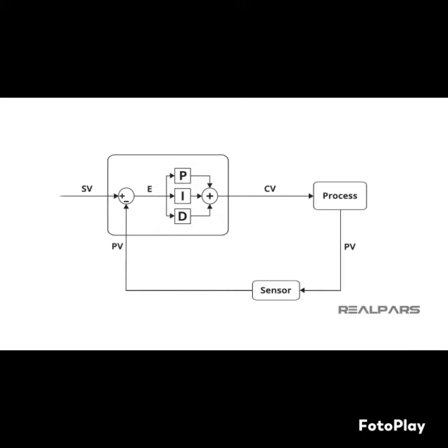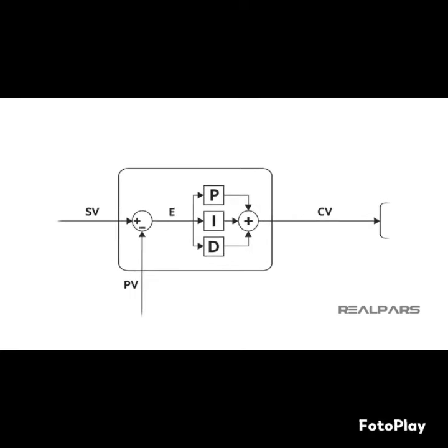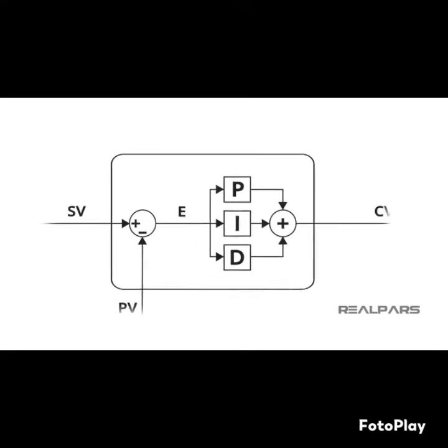In the most simplistic terms, the controller calculates the P, I, and D actions and multiplies each parameter by the error, or E, which is equal to set point minus process variable in direct acting, as discussed previously. Then, all parameter calculations are added up to produce the control variable. Unfortunately, there is no industry standard on the parameter terms. Here are some of the uses found today.